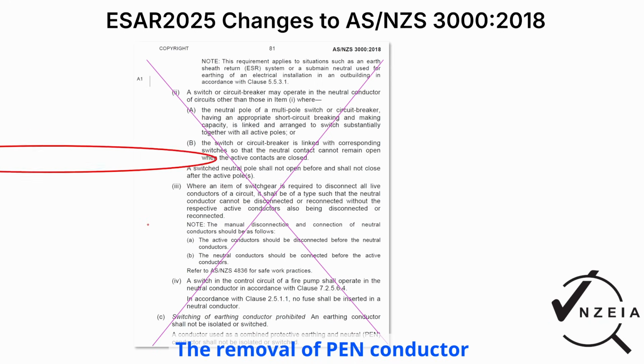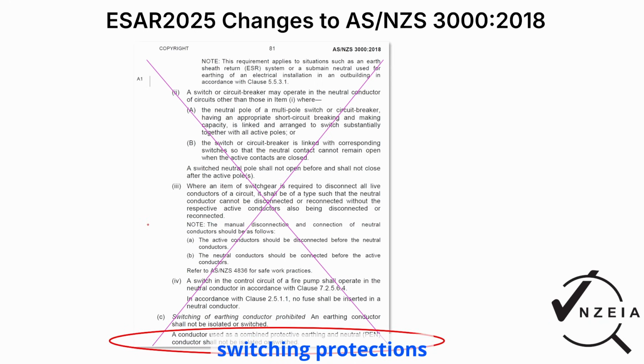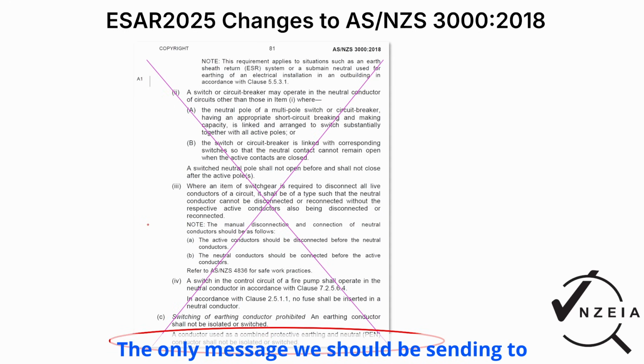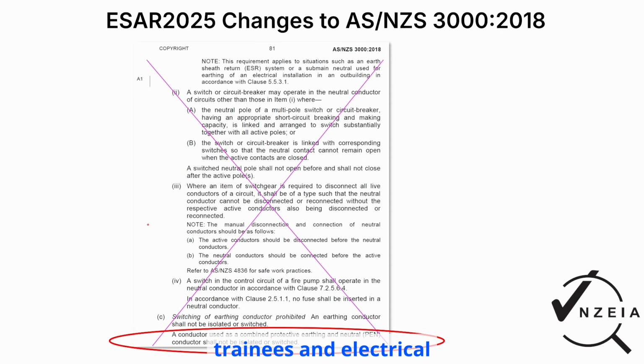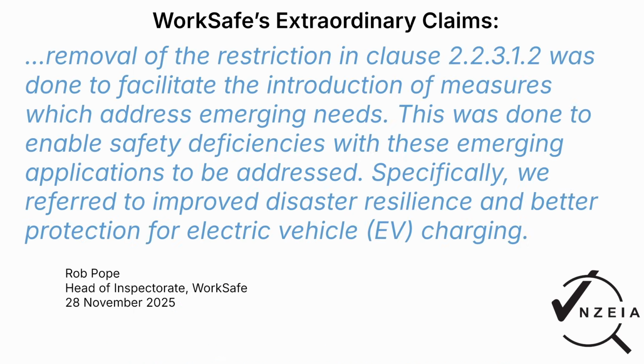The removal of PEN conductor switching protections in subclause C is very concerning. This change lacks the most basic understanding of electrical engineering and competence. The only message we should be sending to trainees and electrical workers is that the PEN conductor is critical to the safety of the installation and must not include any switches, fuses, circuit breakers. The slightest deviation from this message will have negative safety implications.